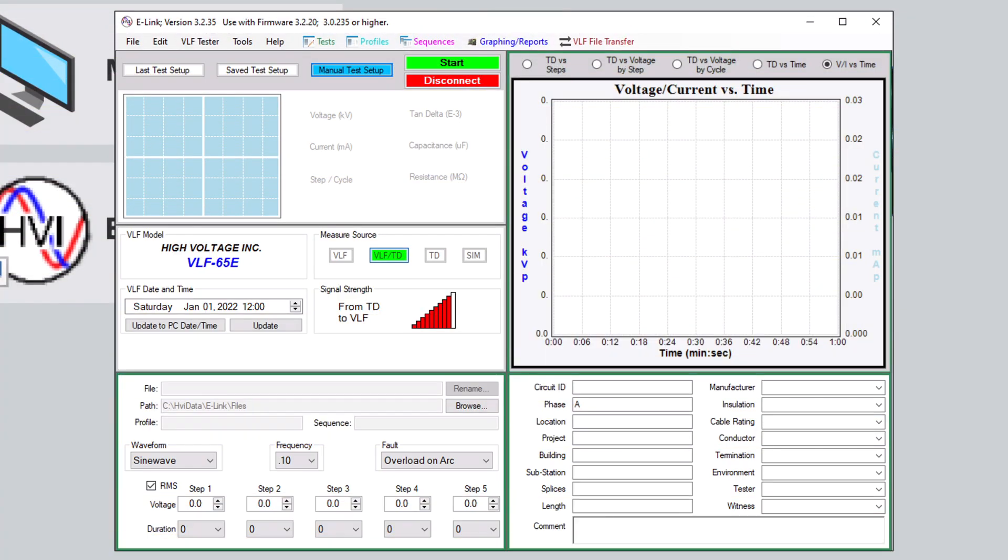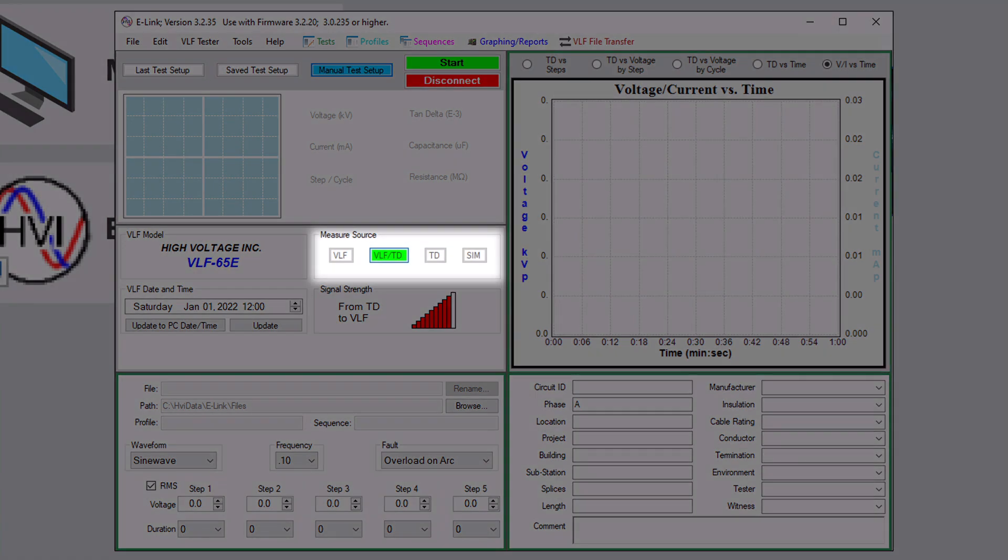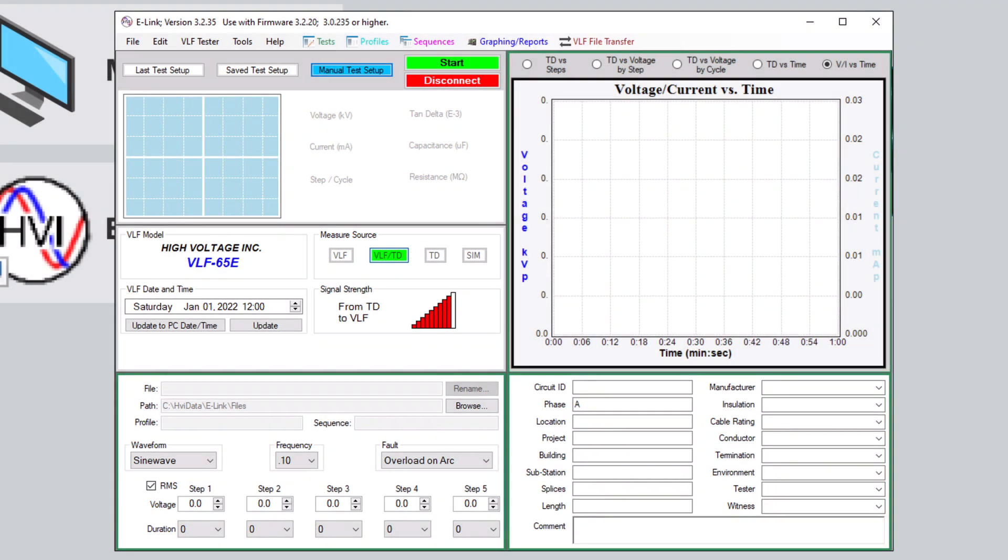Part 3: Running a Tan-Delta test. Whether you are running the Tan-Delta test directly from the front panel of the VLF-E Series hipot, or remotely from an e-link-enabled laptop, you will first need to change your measurement source. The measurement source can be changed from the front panel by entering into the advanced settings. The default measurement source is VLF, but you can change it to Tan-Delta. If using the e-link software, the measurement source is visible on the main test screen next to the signal strength meter. Once you have changed the measurement source to Tan-Delta, you can set up the general parameters of the test.